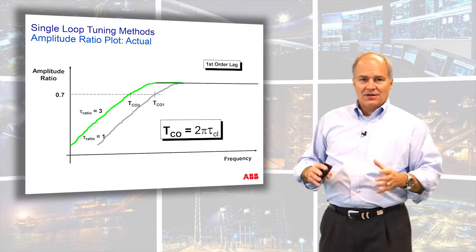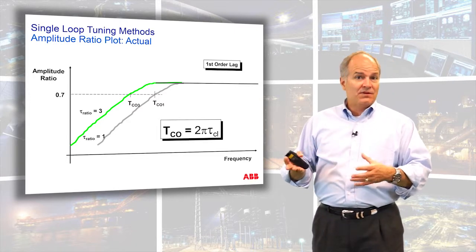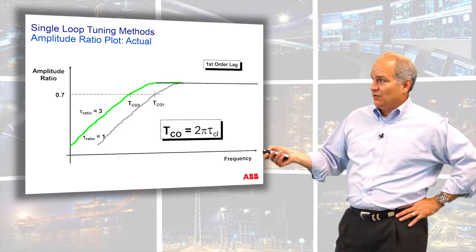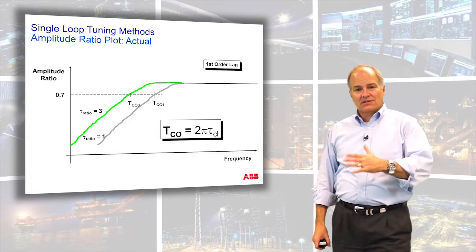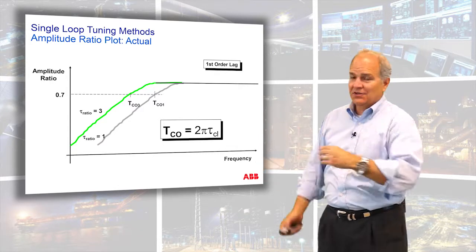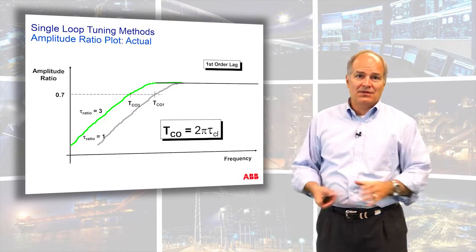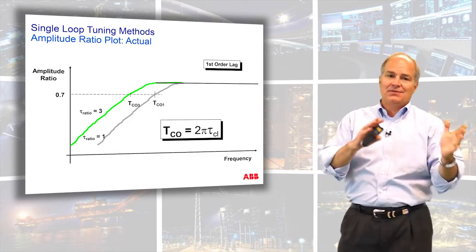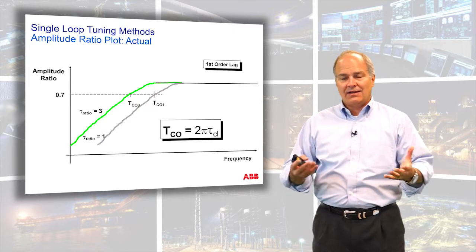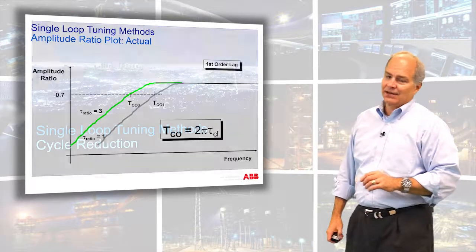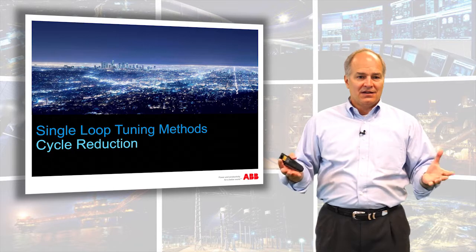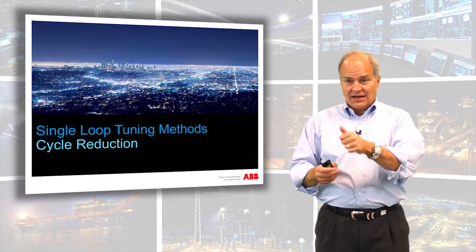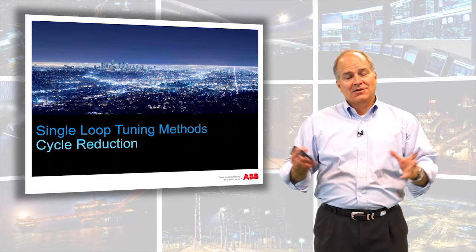I've used this several times to troubleshoot processes. When called in for an oscillating loop, I can say: flip it to manual — if the oscillation goes away, it's a control problem; if it's still there, it's a process problem, not control's fault. As you tune a loop slower and slower, the attenuation curve flattens out, eventually having zero ability to regulate. That's why we recommend tau ratios between one and a half and three. In this talk, we covered dealing with cycles and oscillations: 2π times the closed loop time constant gives you the cutoff period — disturbances slower than that are attenuated; faster ones pass through.